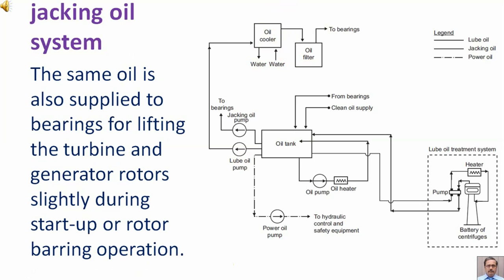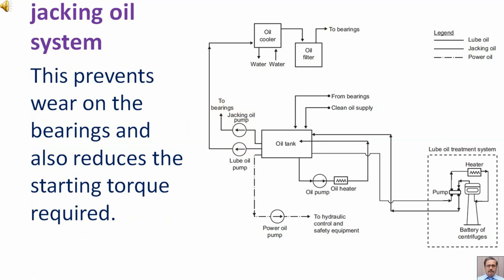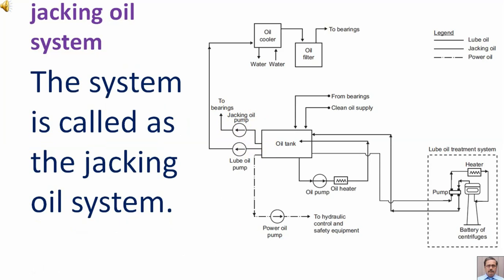The same oil is also supplied to bearings for lifting the turbine and generator rotors slightly during start-up or rotor barring operation. This prevents wear on the bearings and also reduces the starting torque required. This system is called the jacking oil system.